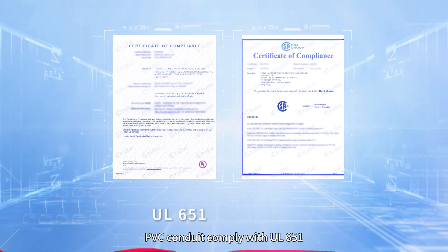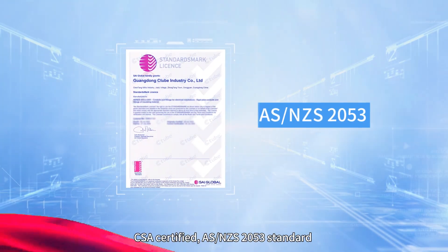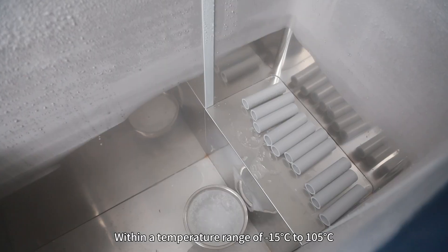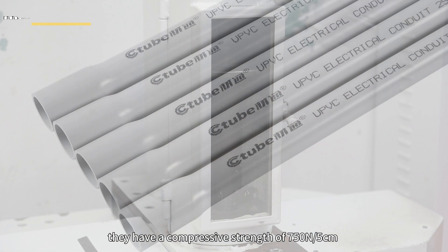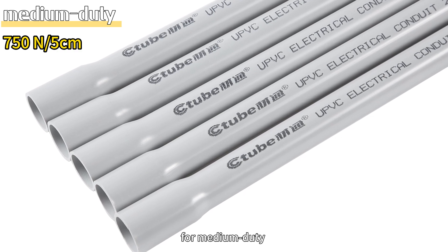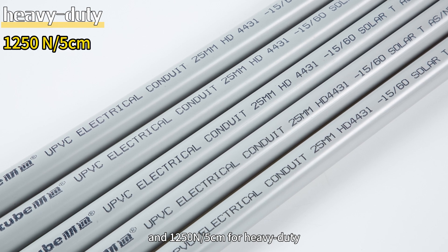PVC conduits comply with UL651 CSA certified and AS/NZS 2053 standards for both PVC and UPVC solar conduits. Within a temperature range of negative 15 degrees Celsius to 105 degrees Celsius, they have a compressive strength of 750 N per 5 cm for medium duty and 1,250 N per 5 cm for heavy duty.